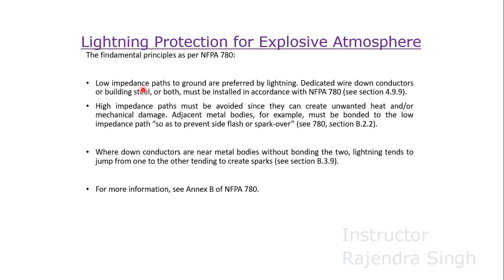A low impedance path to ground is preferred by lightning. Dedicated down conductors or building steel, or both, must be installed in accordance with NFPA 780 Section 4.9.9. High impedance paths must be avoided since they can create unwanted heat and/or mechanical damage. Adjacent metal bodies must be bonded to the low impedance path so as to prevent side flash or spark over.